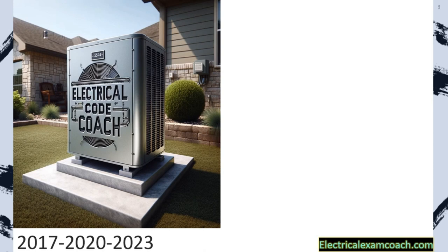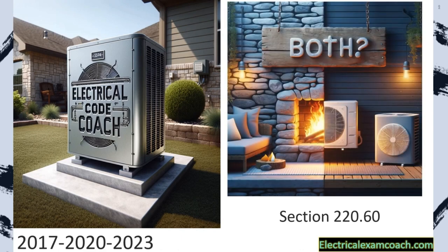Welcome back. I am the Electrical Code Coach from ElectricalExamCoach.com. Today we're going to be calculating HVAC VAs for heating, venting, and cooling. The only code we need to be familiar with is 220.60, which talks about non-coincidental loads. Usually in a typical house, you're not going to be running heating and cooling at the same time, so the code only requires us to count the larger of the two.